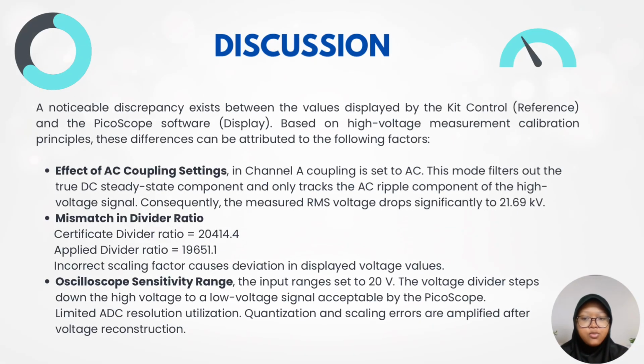On this slide, we can see the primary reasons why the voltage value displayed by the PicoScope differs from the reference value shown by the kit control. The first factor is the AC coupling setting. Since channel A is configured in AC coupling mode, the oscilloscope removes the DC component of the signal and only measures the AC ripple. As a result, the displayed RMS voltage drops significantly to around 21.69 kV.